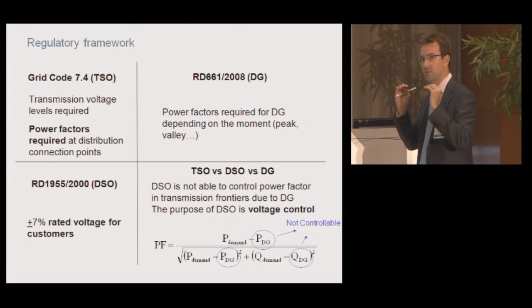In distribution, very easy, we have to maintain the voltage in a margin, in a range of 7%. And for distributed generation, they have to maintain fixed power factors in different time scales. So we only have a time discrimination. But this time discrimination, and we are going to remark this in conclusions, this time discrimination is for the whole country. But reactive power is a local phenomenon. I will remark this in the conclusions.